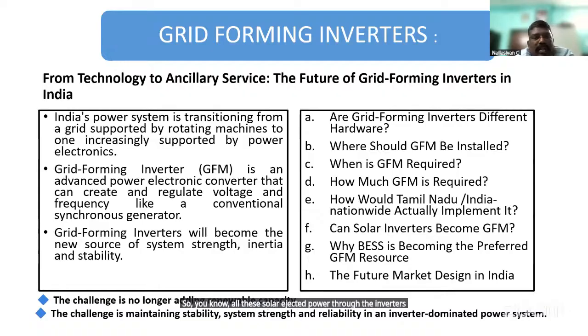The grid forming inverter is nothing but an advanced power electronic converter that can create and regulate voltage and frequency like a conventional synchronous generator. This is the actual meaning and term found in the book and in publications from Grid India reports. I repeat, a grid forming inverter is an advanced power electronic converter that can create and regulate voltage and frequency like a conventional synchronous generator.